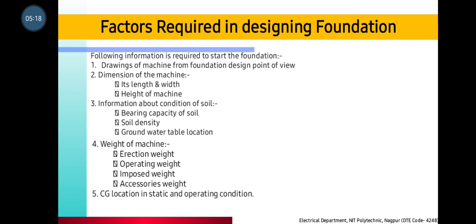CG location in static and operating condition. The level of plinth should be above the maximum flood level of the site. If there are many places where there is an open site where a motor is installed — for example, many places like water pumps, large societies with a water pumping system which is an open site — so you have to make the foundation according to the flood level.